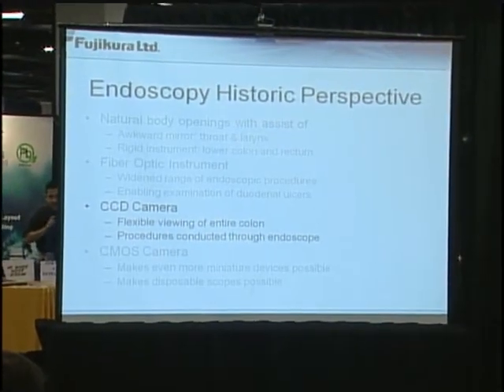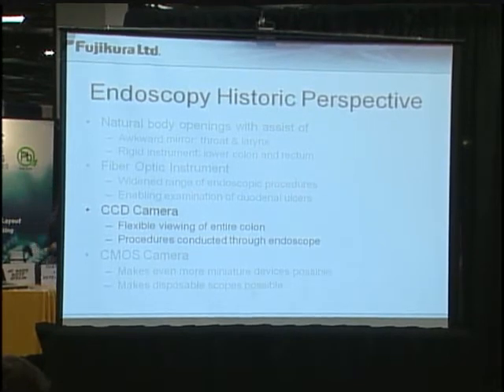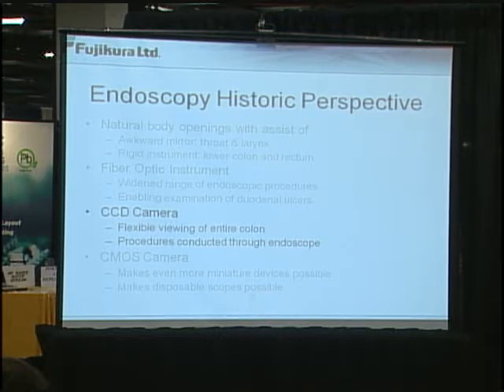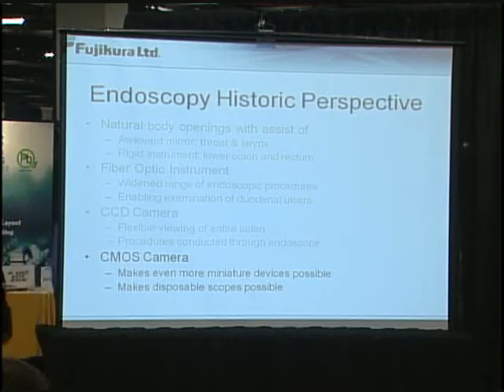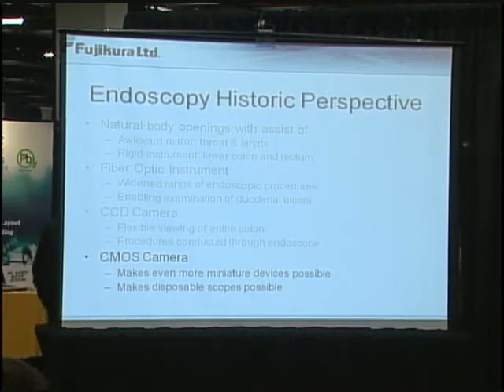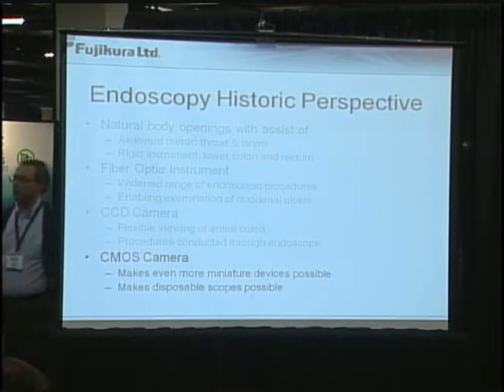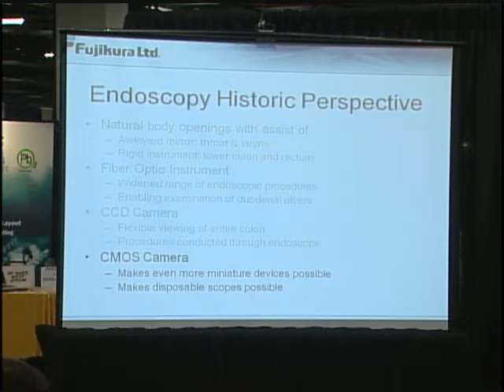With the introduction of CCD cameras, this brought very flexible viewing of the entire colon, and procedures could be conducted through endoscopes. When we move to the CMOS camera era, because of the size and many other benefits CMOS can provide, this makes even more miniature devices possible. Because of the low costs at very high volume for CMOS technology, this makes disposable scopes available.